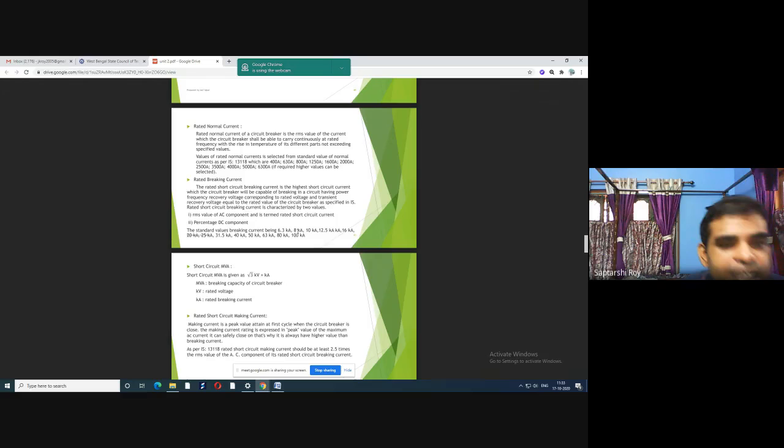Values of rated normal current are selected from the standard values of normal current as per IS 13118, which are 400 ampere, 630 ampere, 800 ampere, 1250 ampere, 1600 ampere, 2000 ampere, 2500 ampere, 3500 ampere, 4000 ampere, 5000 ampere, 6300 ampere. The required higher value can be selected.